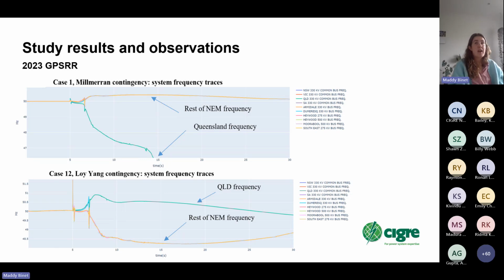We also saw that for a lot of the daytime cases, a significant amount of DPV could also trip based on inverter settings due to the frequency falling below 49 hertz when UFLS starts to operate. So that as well could increase the contingency size quite significantly in terms of the amount of generation that's tripped off.